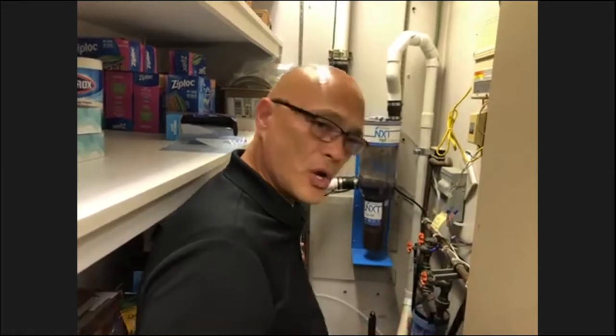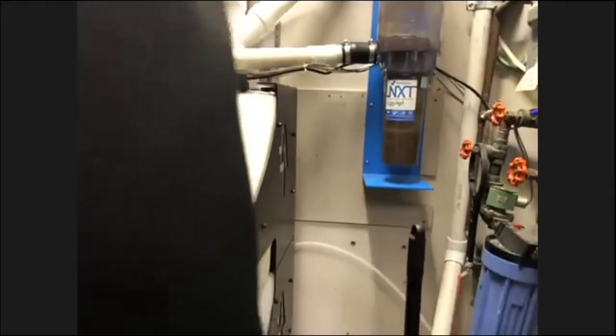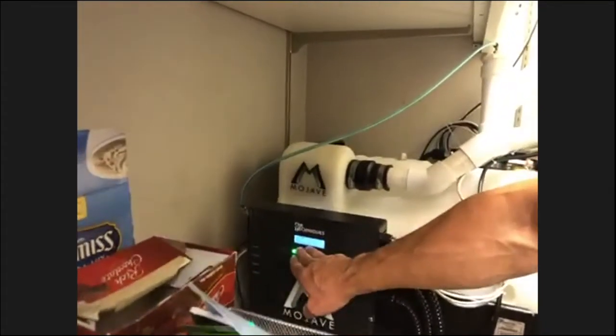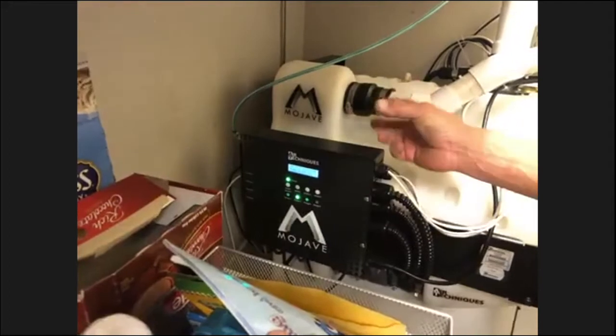All the liquids are stored in these big tanks here through the day, and they fill up. At the end of the day, they dump, and then there's a water washout that washes them out. The control is actually right here. This tells you pump one is at zero and pump two is at 50, so it's monitoring the two different pumps all the time.